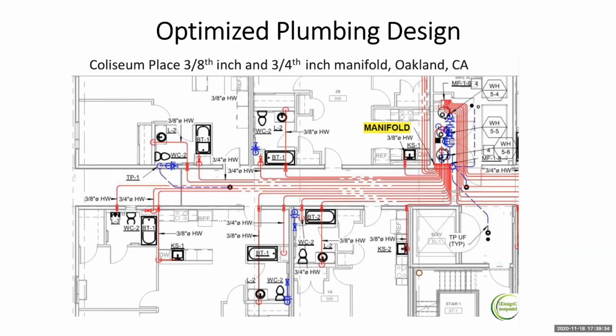This is a better illustration. This is where we're using 3/8-inch piping for most of what's being delivered here. People frequently use 3/4-inch piping, which has 4 times as much water in it as 3/8-inch piping, so you have to purge 4 times as much water before you get hot water. This leads to a lot of hot water waste because you use your little bit of hot water and then have this huge pipe full of hot water still sitting there. It cools off, you lose heat, and you're never getting your hot water quickly or efficiently.